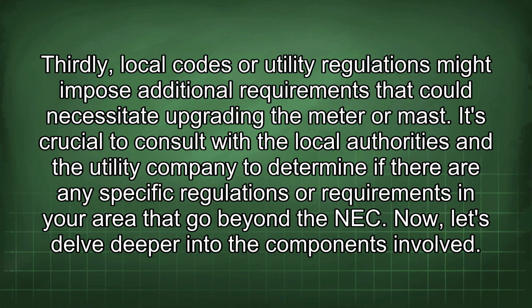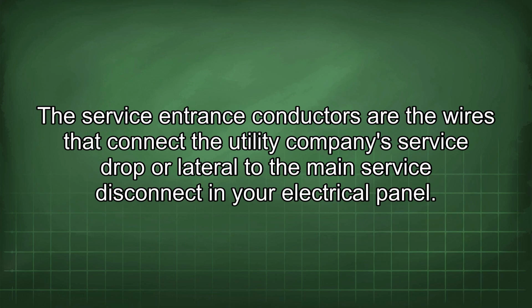Thirdly, local codes or utility regulations might impose additional requirements that could necessitate upgrading the meter or mast. It's crucial to consult with the local authorities and the utility company to determine if there are any specific regulations or requirements in your area that go beyond the NEC. Now let's delve deeper into the components involved. The service entrance conductors are the wires that connect the utility company's service drop or lateral to the main service disconnect in your electrical panel.